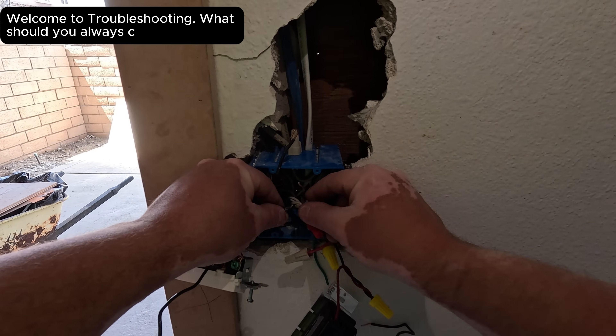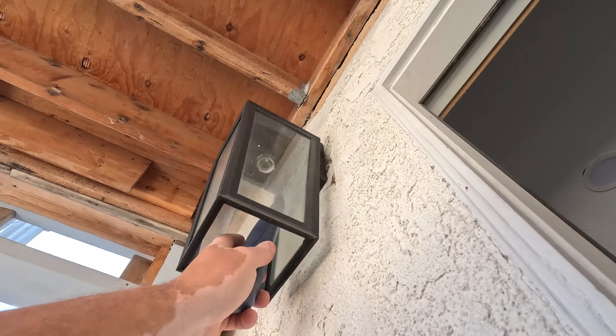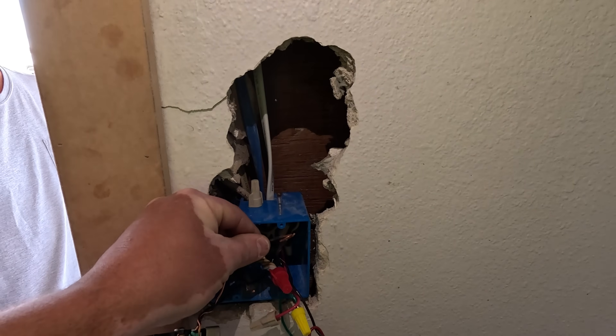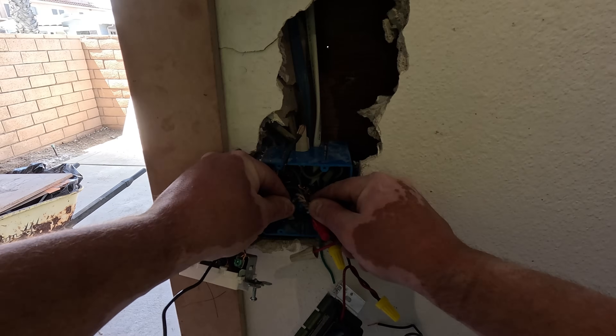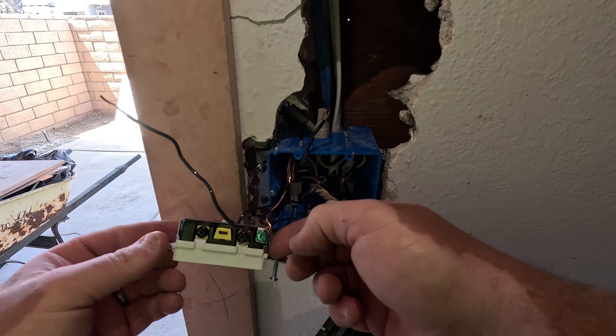That's it — it was wired right. I didn't jack it up. There's that light — we know that one. This one going down to the receptacle. Cover that neutral up real quick. It's working — the LED light bulb outside is working. So then the other one — plug tester. What in the world is going on? You had your hot tailed out to go to the hot side — the black is your hot, right?